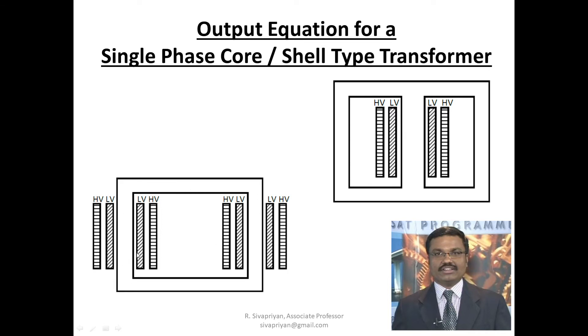In a core type transformer, the winding is placed on the limb. The primary (LV) winding is divided into two parts — half on one limb and half on the other limb. Similarly, the HV winding is also split: half on each limb. In the shell type transformer, the winding is placed on the center limb — the entire LV and HV windings are placed there, either in cylindrical or sandwich pattern. This figure shows the cross-sectional view of the single-phase core type and shell type transformers.